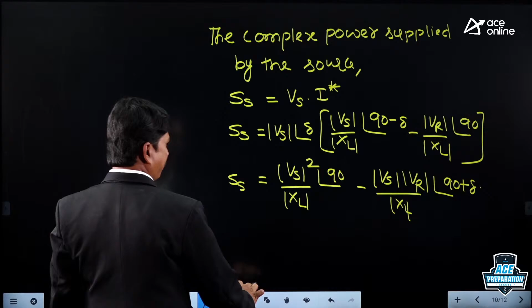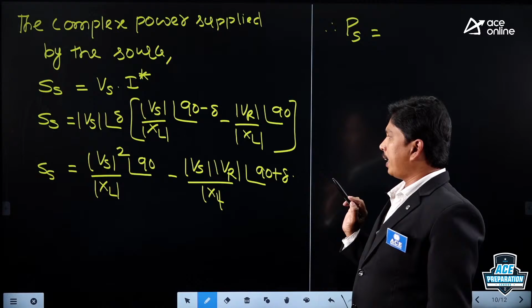And from this equation, we can calculate the total active power and the reactive power. Once we have the polar term, how do we calculate the active power? The active power supplied P is equivalent to Vs square divided by XL cos 90, which will be 0, and Vs Vr divided by XL cos of 90 plus delta, which will be minus sin delta. So we get Vs Vr divided by XL sin delta. Vs Vr divided by XL sin delta is the active power equation we are having.